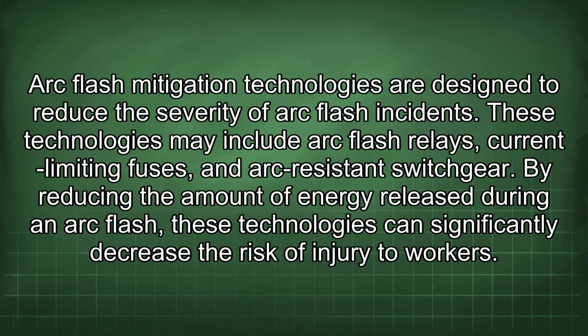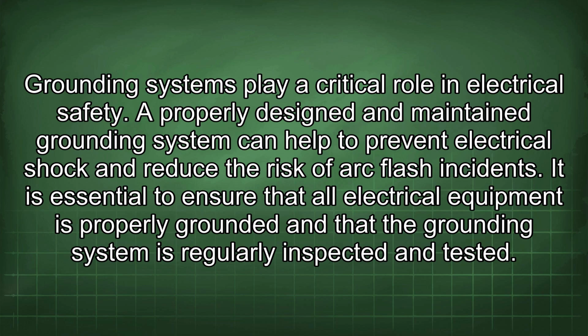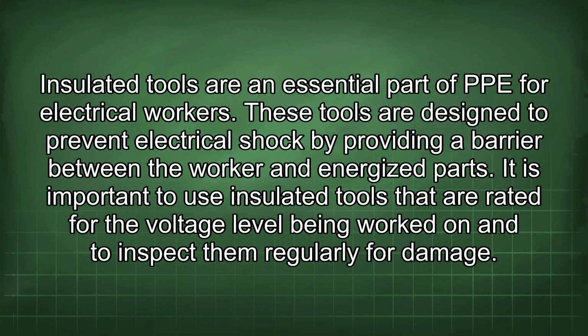Grounding systems play a critical role in electrical safety. A properly designed and maintained grounding system can help to prevent electrical shock and reduce the risk of arc flash incidents. It is essential to ensure that all electrical equipment is properly grounded and that the grounding system is regularly inspected and tested. Insulated tools are an essential part of PPE for electrical workers. These tools are designed to prevent electrical shock by providing a barrier between the worker and energized parts. It is important to use insulated tools that are rated for the voltage level being worked on and to inspect them regularly for damage.